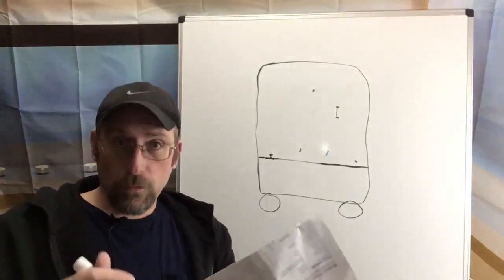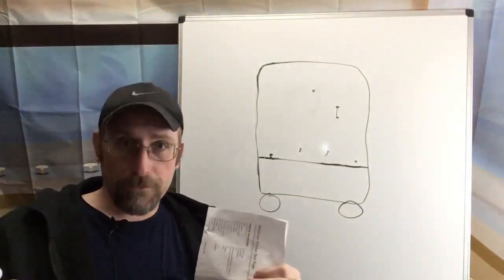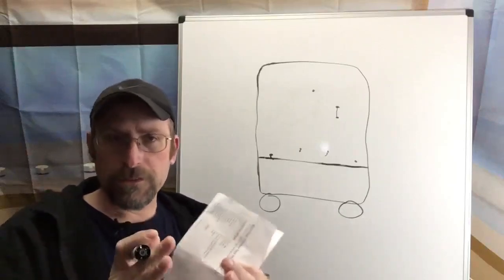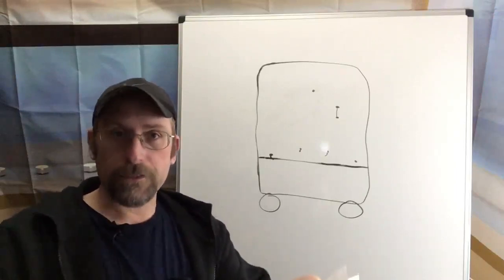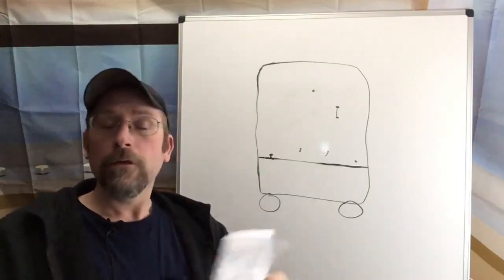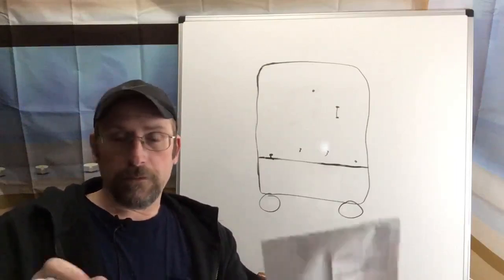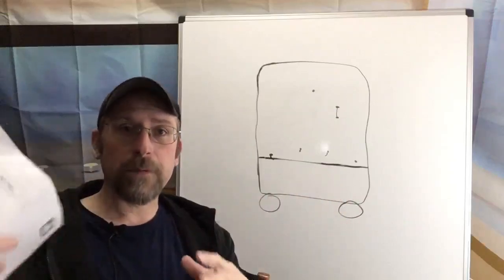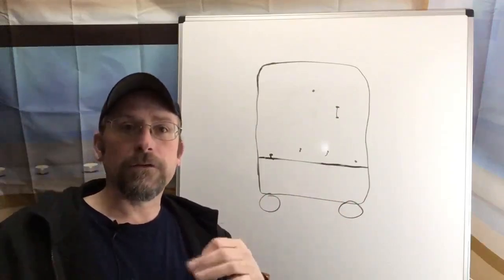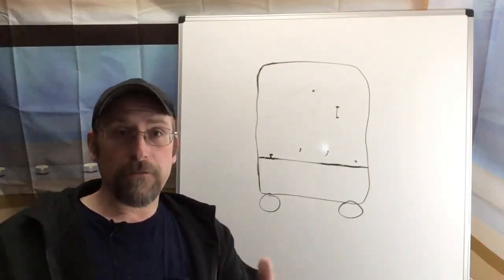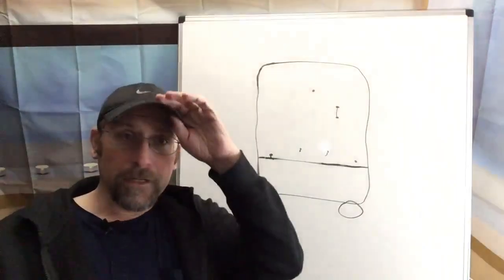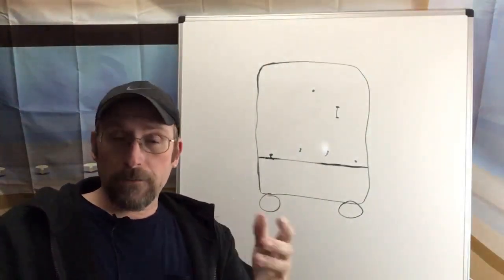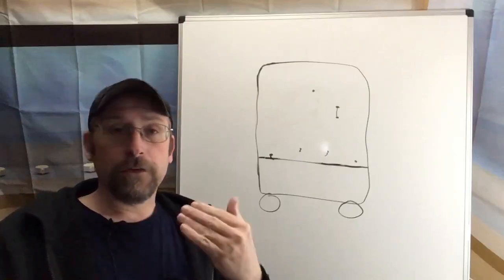If the person can't sleep with it, usually what I do is we talk about adding some more oxygen tubing and taking it into another room or into the hallway. I start with the hallway if it's really small or they don't want it there or it's a restriction, like they're using a walker or something, then we start looking for another room. But what we don't want is a closet, because a closet is a really confined space. It's not going to allow the oxygen machine to breathe. We need it to breathe. We need it to have air so it's not being confined because that's going to cause even more problems.